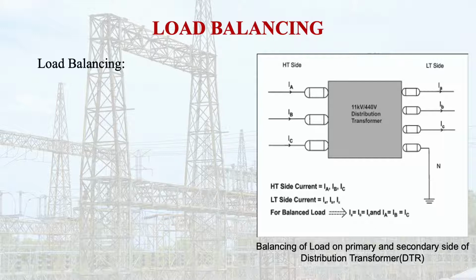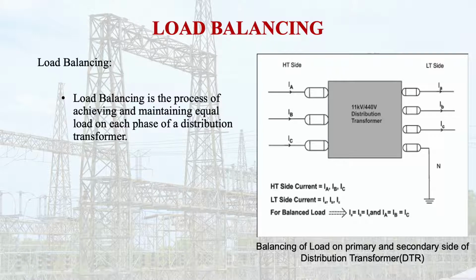What is this, and how is the load balancing done, and what does it mean first. So load balancing is the process of achieving and maintaining equal load on each phase of the distribution transformer. You know that a distribution transformer converts the primary distribution voltage, suppose 11 kV, to 400 volt. Similarly, from 33 kV to 11 kV. So these are connected in a star delta manner, so three-phase supply is given on the input side, and the three-phase output is obtained from the secondary side, and the voltage level is changed.